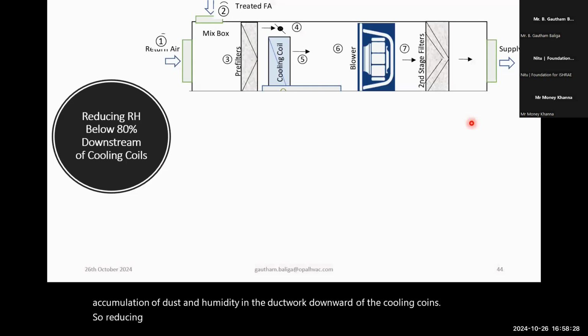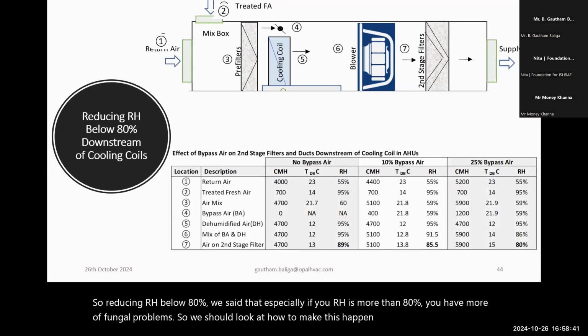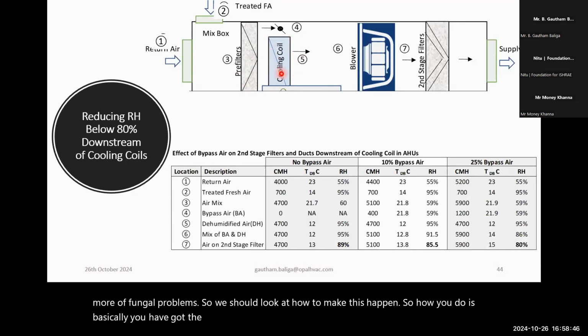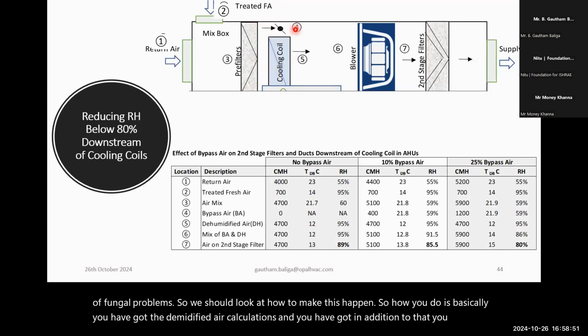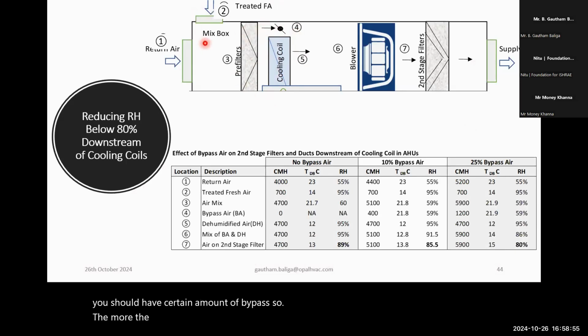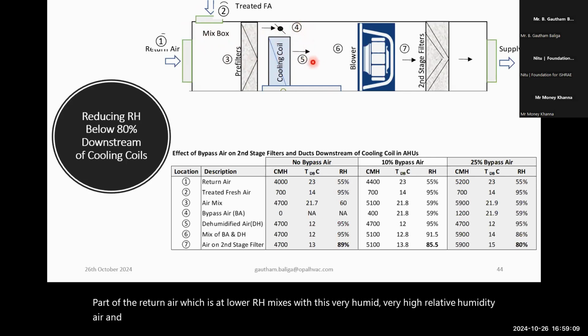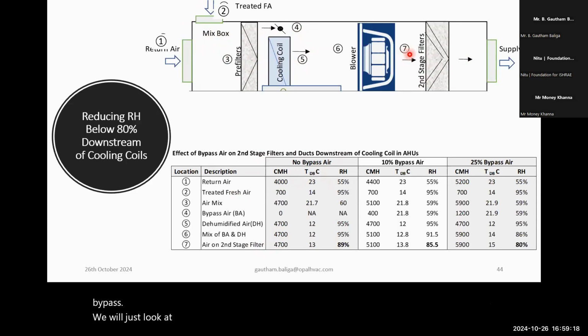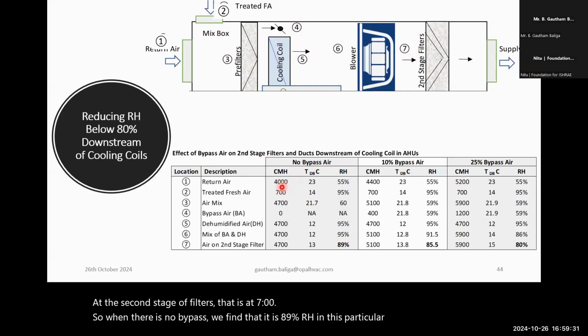So reducing RH below 80%: we said that especially if your RH is more than 80%, you have more fungal problems. So we should look at how to make this happen. How you do it is basically you have the dehumidified air calculations, and in addition to that, you should have a certain amount of bypass. The more the bypass, it means part of the return air, which is at lower RH, mixes with this very humid, very high relative humidity air, and decreases the relative humidity post this cooling coil. So if you can see, when there is no bypass, we'll just look at what is happening at the second stage of filters, that is at 7. When there is no bypass, we find that it is 89% RH in this particular example.